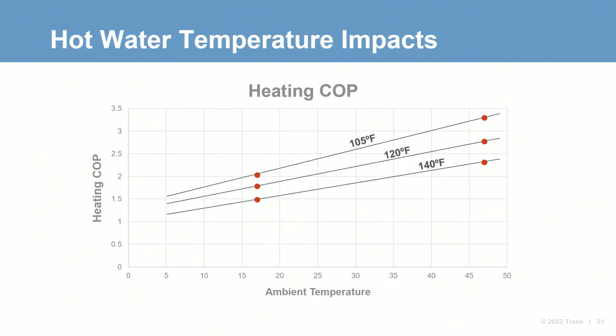We've connected the points with a linear slope to show the general trend. The first thing that pops out is that the COP drops as the ambient temperature decreases, regardless of supply hot water temperature. This seems rather intuitive. The second thing to note is the increased efficiency requirement for lower hot water temperatures. Unit efficiency increases dramatically as the hot water set point decreases, and we can more easily achieve higher efficiencies.